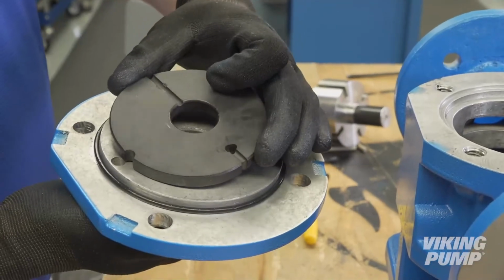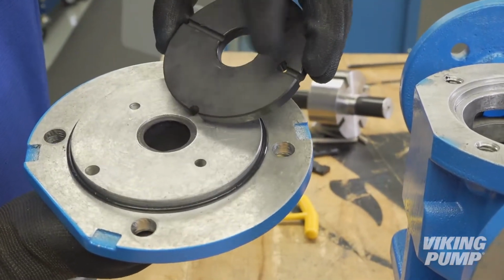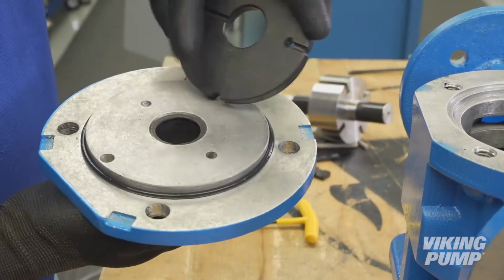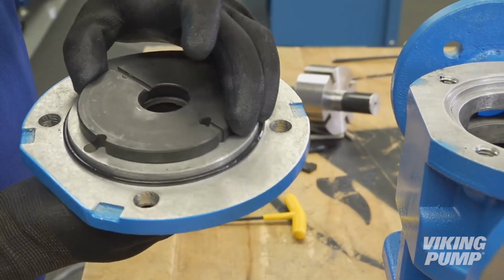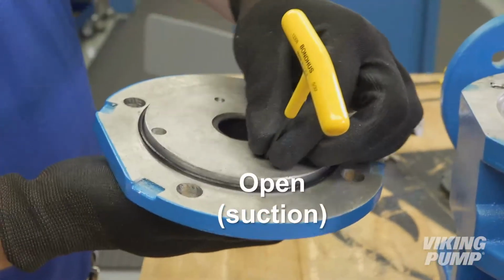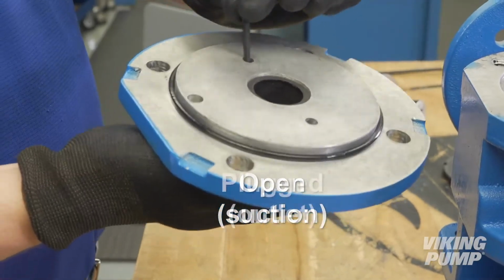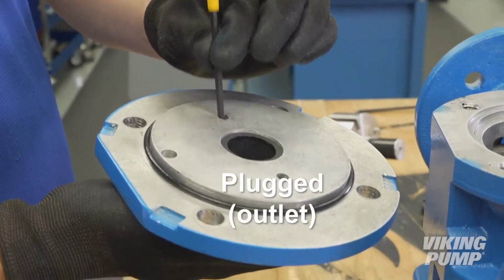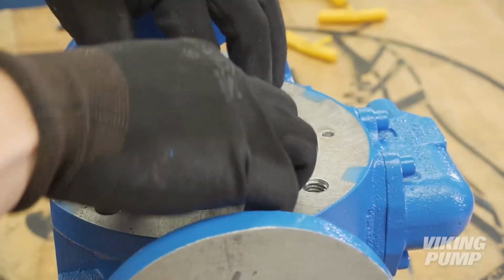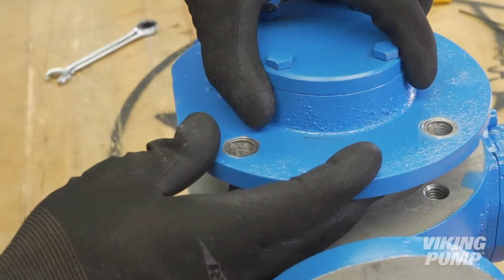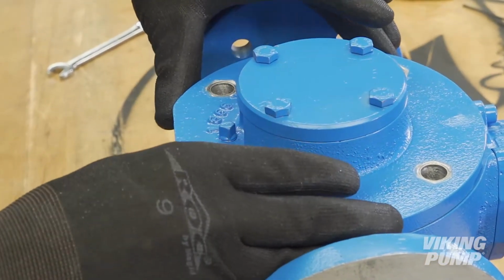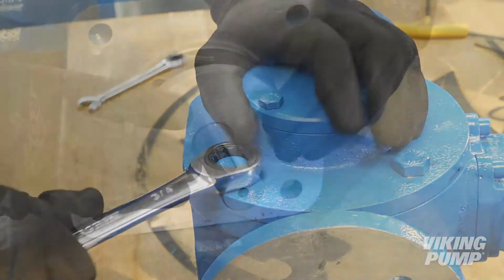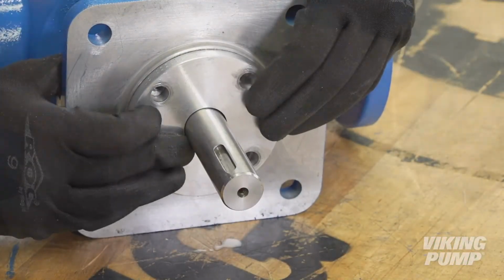Reinstall the final carbon disc and the pump head. Make sure to line up the hole in the disc with the open hole on the suction side of the head. A screwdriver or Allen wrench can be used to confirm which side is plugged. Finally, reinstall the seal and seal gland.